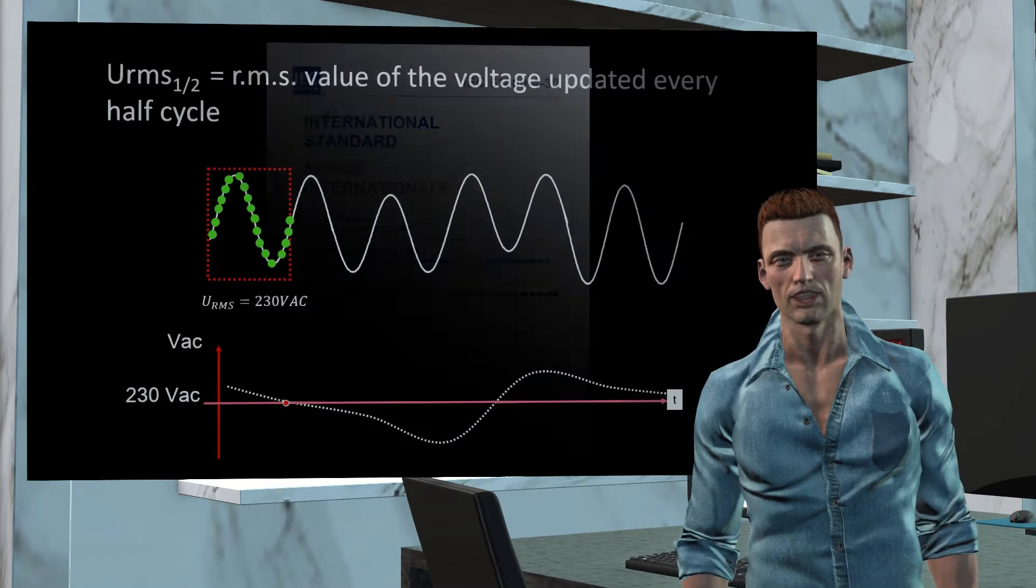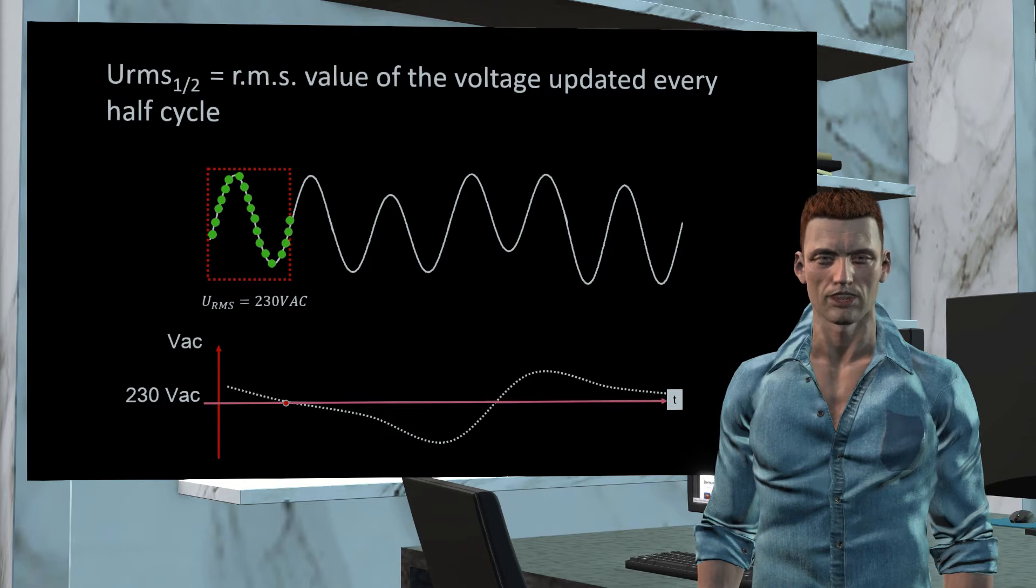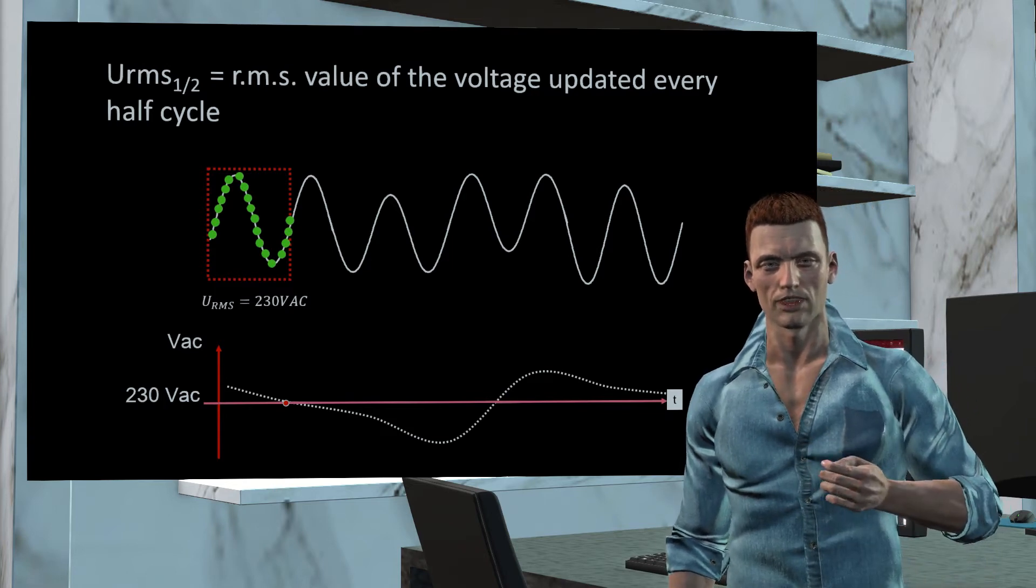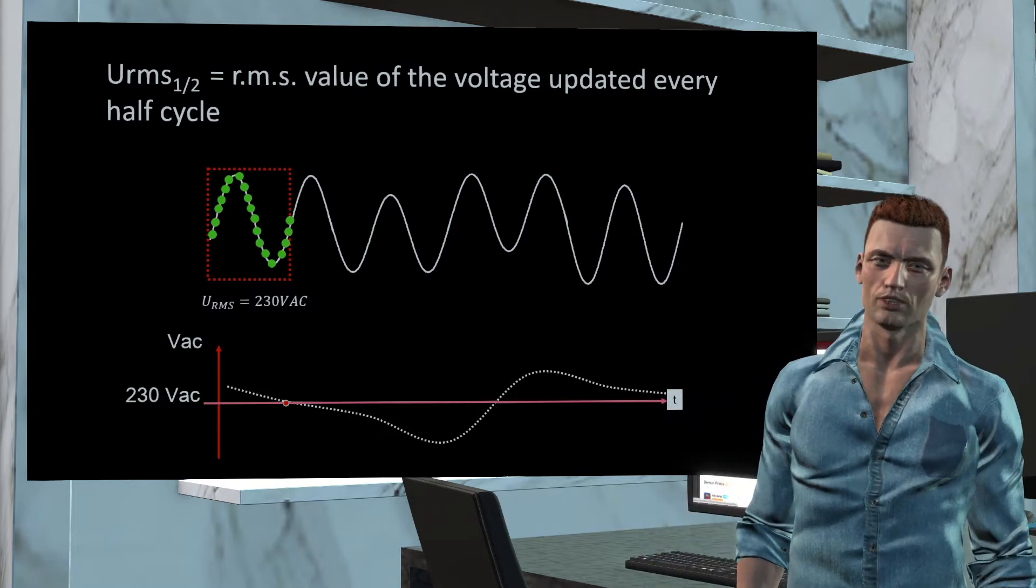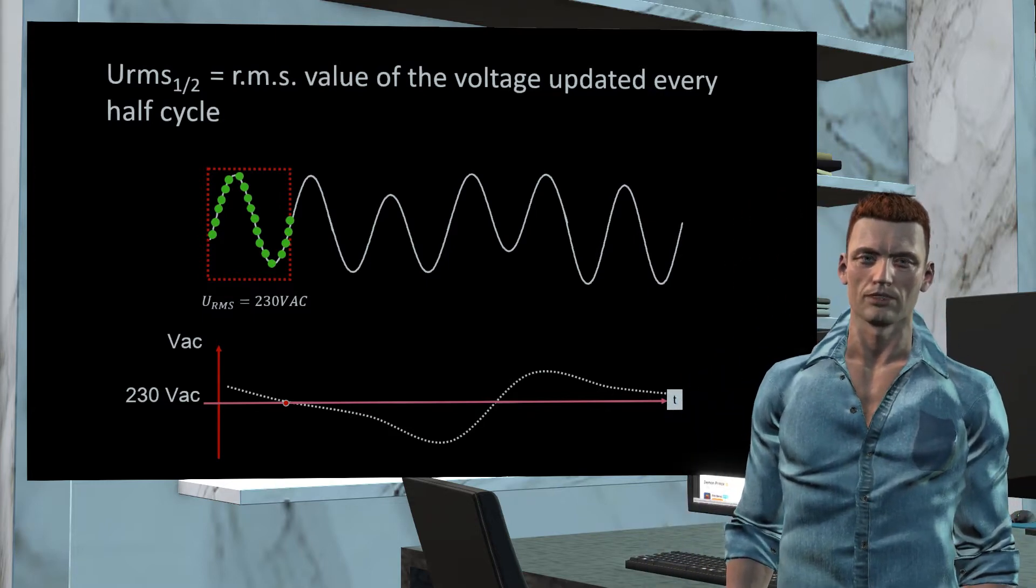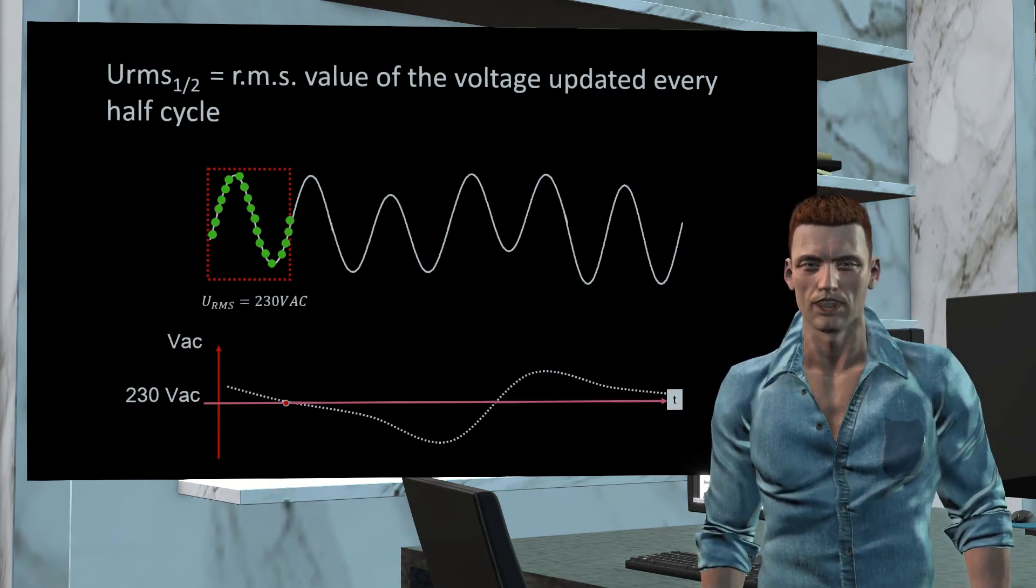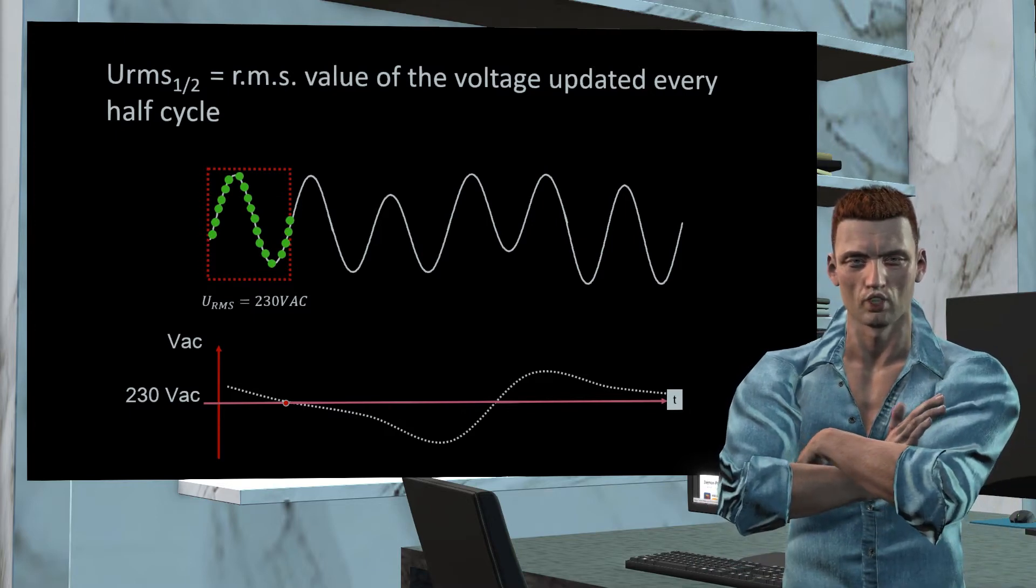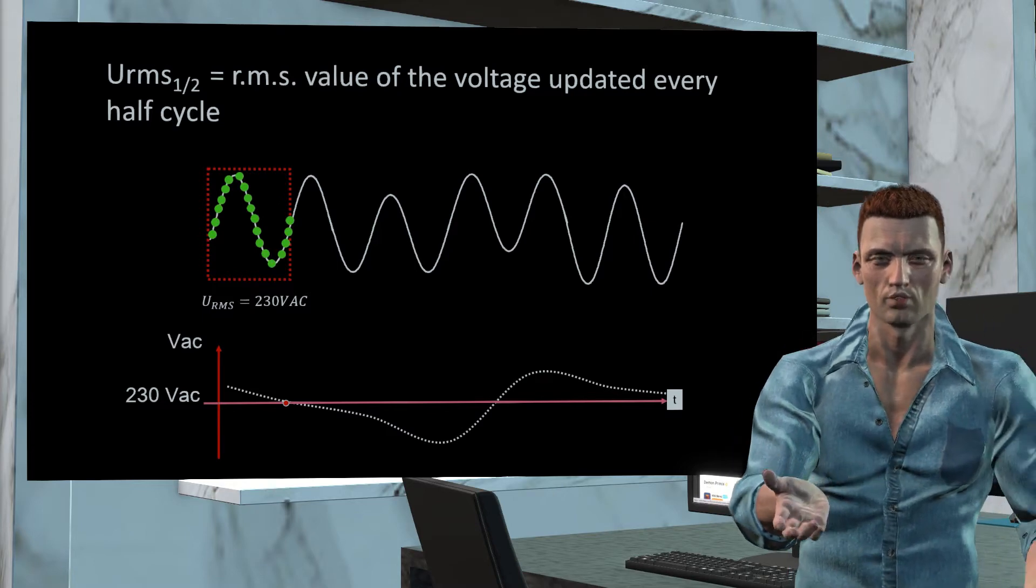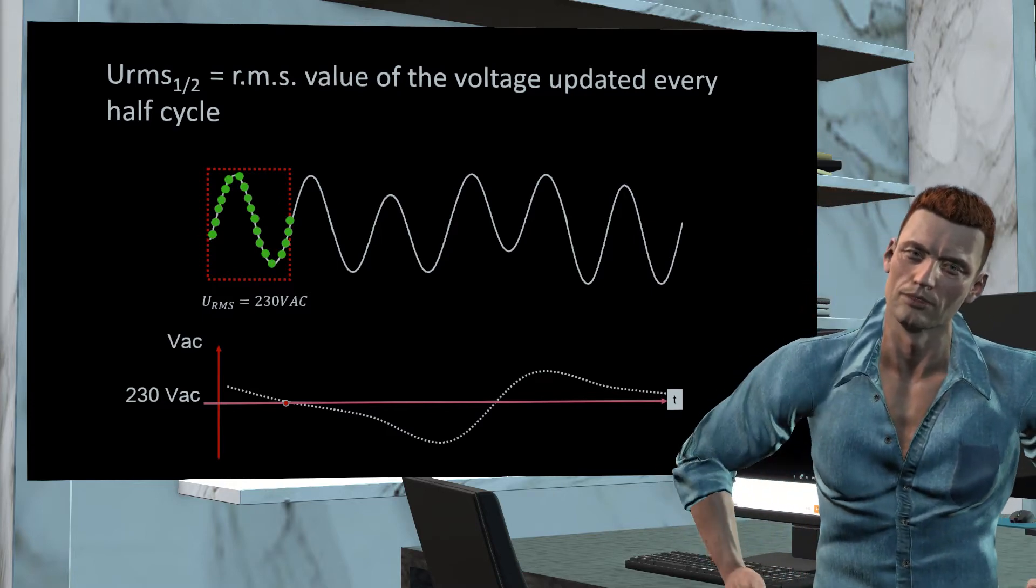This standard defines the concept of effective half-cycle value. In this case, the effective RMS value is calculated with the samples taken during a complete cycle, starting with the zero crossing of the wave, and this value is updated every half cycle. As we can see in the image, the analyzer takes the waveform samples obtained during a complete cycle, that is, 20 ms for a frequency of 50 Hz and 16.6 ms for 60 Hz networks, and calculates its associated effective value.